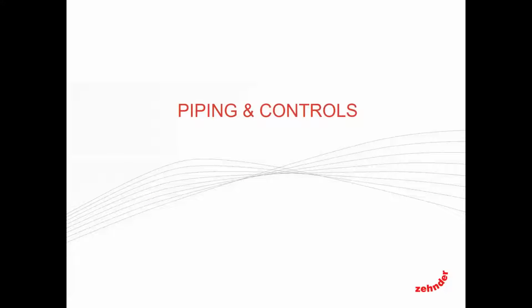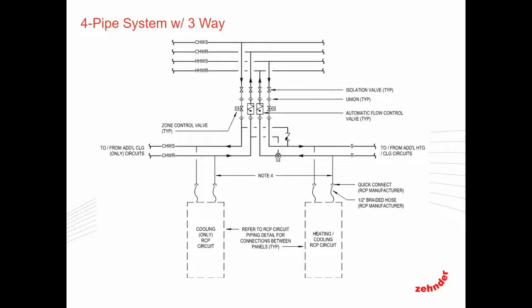All right, piping and controls. I pulled 2 examples that I see most of the time being utilized to control these systems. There's a number of different ways to do this, but these are probably the two most popular designs I've seen. In this application, I have a 4-pipe system. I have a cooling-only circuit, and I have a heating and cooling circuit. This can be a single zone, so you could have cooling-only panels in the interior core space, and then heating and cooling panels along the perimeter, or these can be 2 separate zones completely, 2 separate rooms. There are a couple of different ways of looking at it, but generally your chilled water pipe would open, your 2-way valve would open and pass through into your cooling circuit, and then return through your 3-way valve back into the return side.